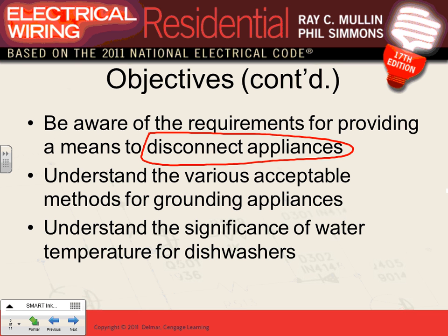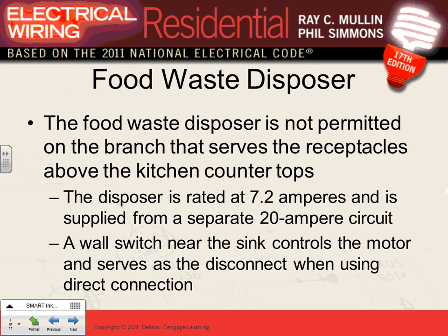Cool. So those are the methods of grounding appliances. It used to be in the past that you could use the grounded conductor to ground dryers and ranges. The grounded conductor, the neutral, no longer applies. So as far as you guys are concerned, being designers moving forward, for every appliance, 99% of what you are going to be dealing with, it's going to be 3 hots for the 3-phase, sometimes a neutral if you need a neutral, and always a grounding conductor, an equipment grounding conductor. So you always have to pull an equipment grounding conductor. Don't worry about the old days, how they did it. Understand the significance of water temperature for the dishwasher. That's just FYI only, for information, so you don't burn yourself, basically.